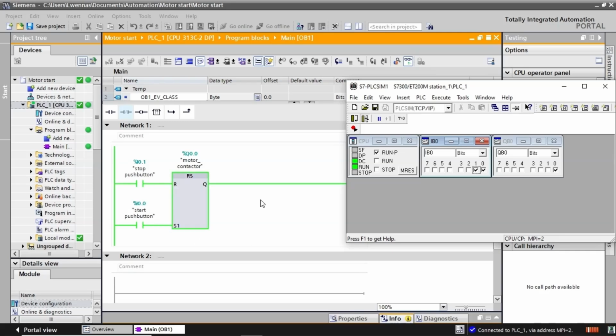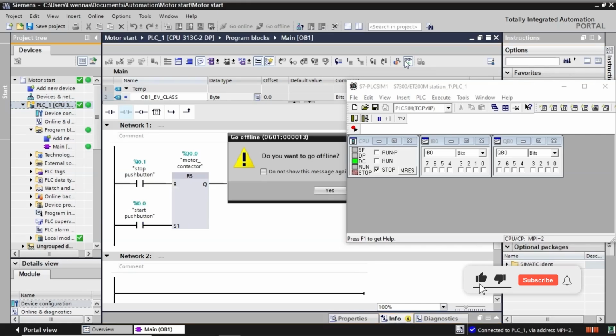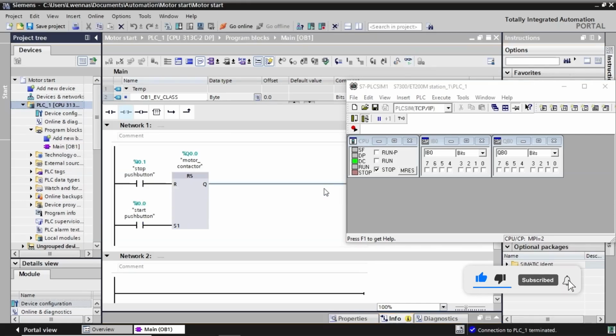In a nutshell, the number 1 next to the R in the SR means that it's the reset which has the priority over the set. Meanwhile in RS, it is the set. It's noteworthy to point out that it's the SR that is most used in PLC programs, but in the world of industry there could be situations where it's the things we held as insignificant that will get us out of trouble, save us time and costs.